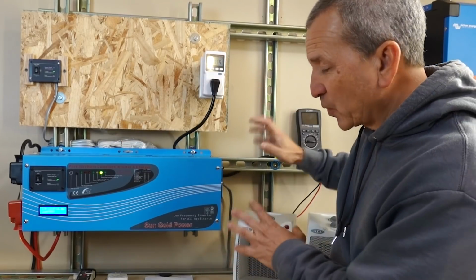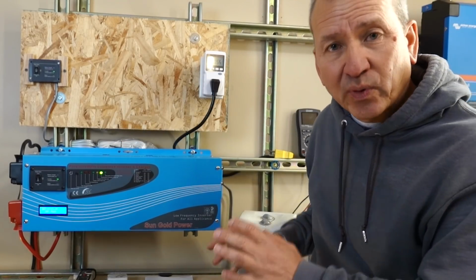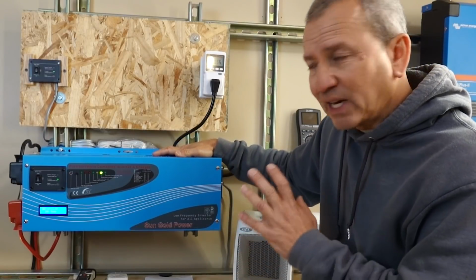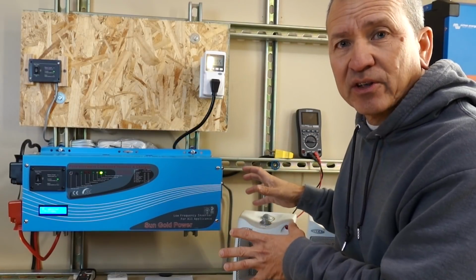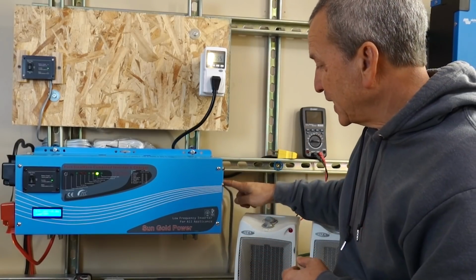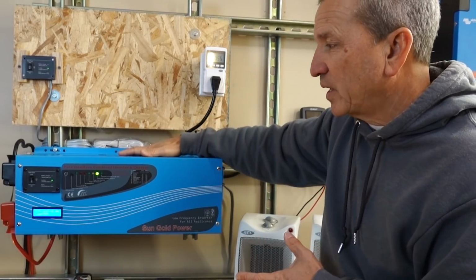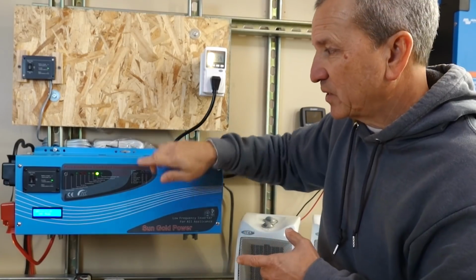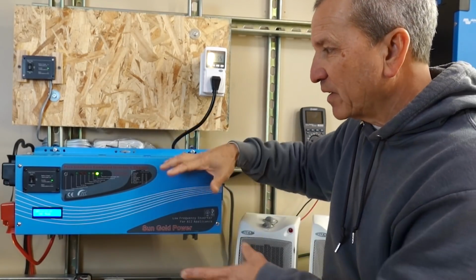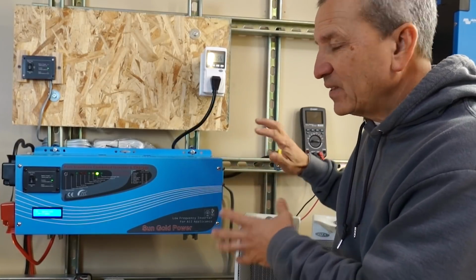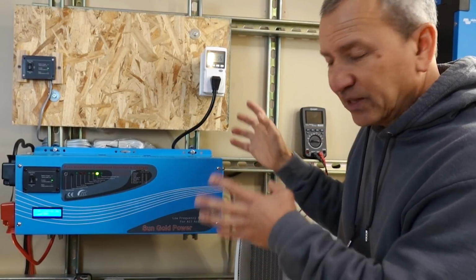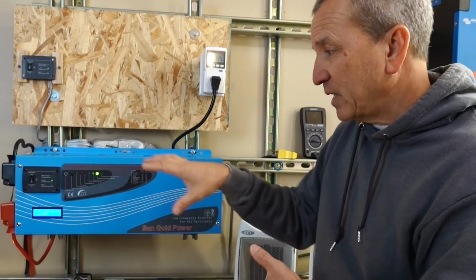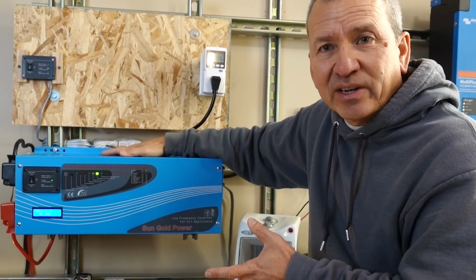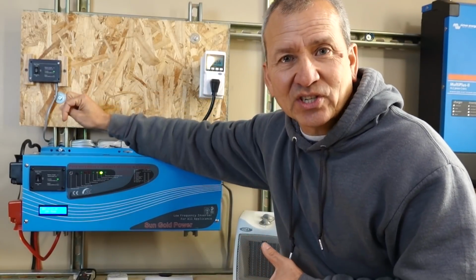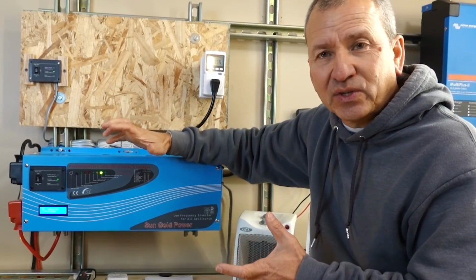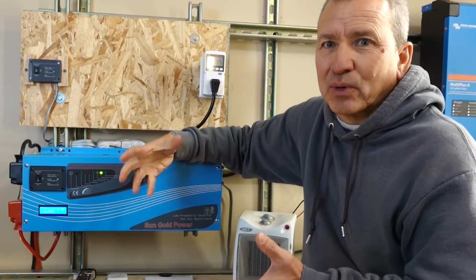One of them is the grid versus battery priority mode. It's preset when you get it to be in AC priority mode. What that means is that if there is AC power coming in, it's going to run in that AC pass-through mode, and it's going to enable the battery charger and all that stuff as long as there's AC power. Now when that AC power drops off for any reason, then it's going to switch to battery power and be in inverter mode. So that's the AC priority. Now with a quick little dip switch setting in the back, you can switch it to battery mode, and they call it like solar mode.